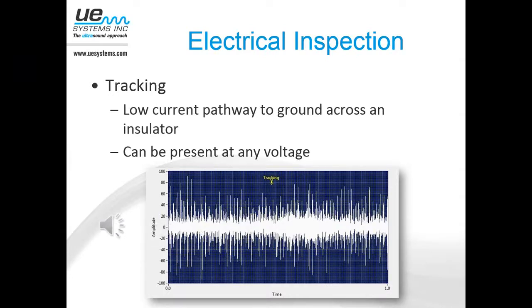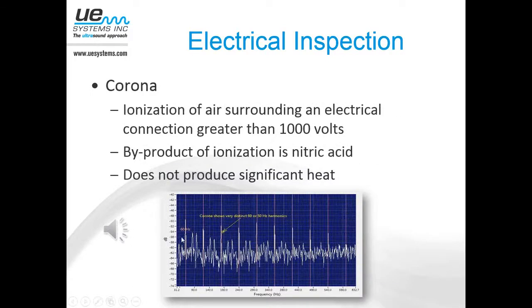I don't know if you can hear that very well, but it's a very consistent buzzing sound. And here's what we call a time waveform, basically a sound recording from that corona. You can see here very distinctive 60-cycle harmonics in the spectrum, but then there's a lot of white noise in between those harmonics, and that's a very classic signature for corona.